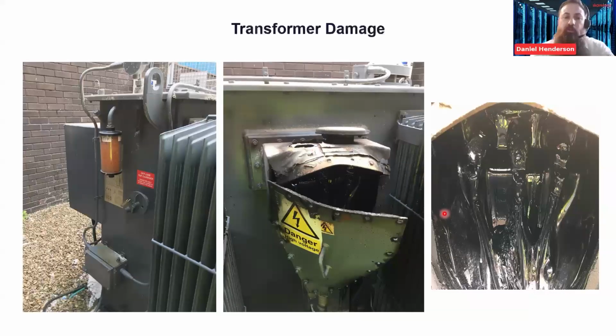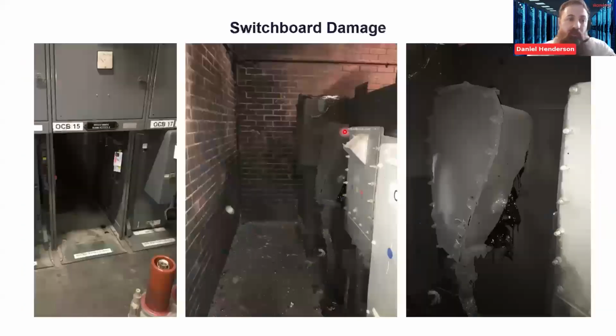Again, for those that aren't familiar, this is a compound filled junction box. So the age of this transformer, it was common practice that they would make the connections and the terminations, and then they would, through this filling cap here, fill the junction box up with a bitumen-based compound, just to make it, I suppose, maintenance free. You're not going to go back in there. The connections are done, and you're not going to take them back off. At the switchgear, this is a front view with the circuit breaker removed.